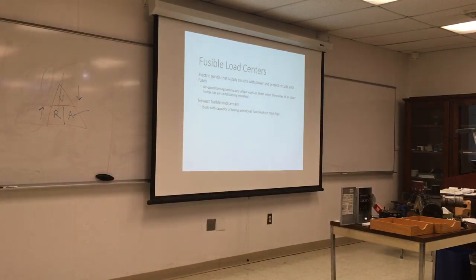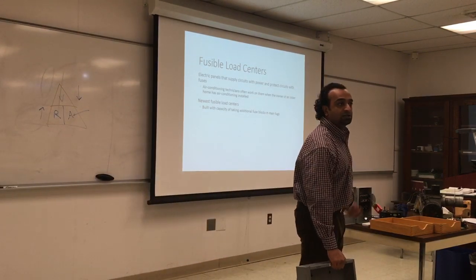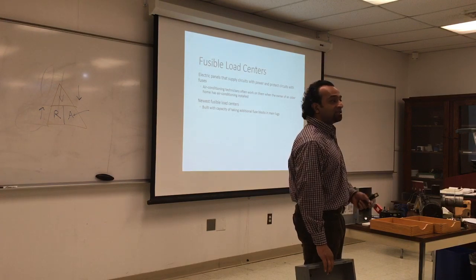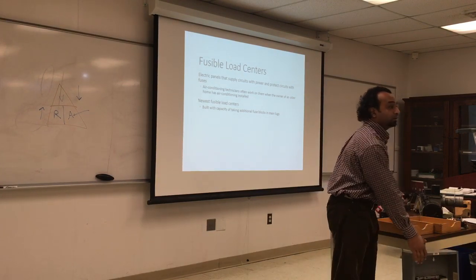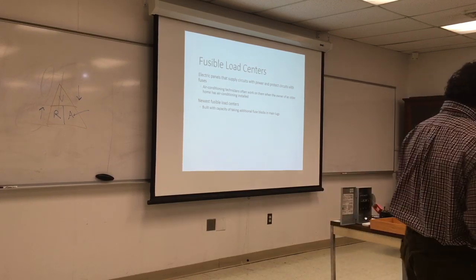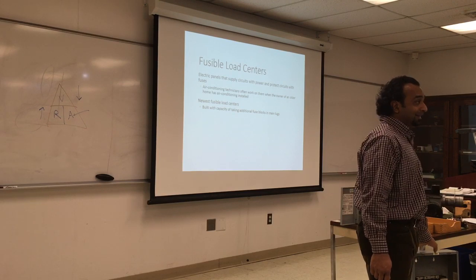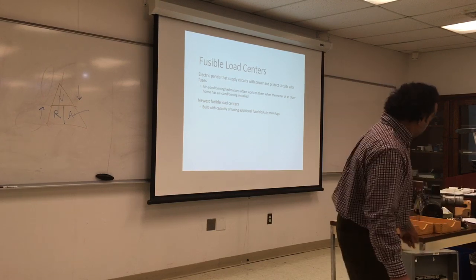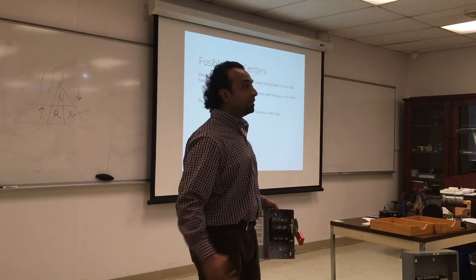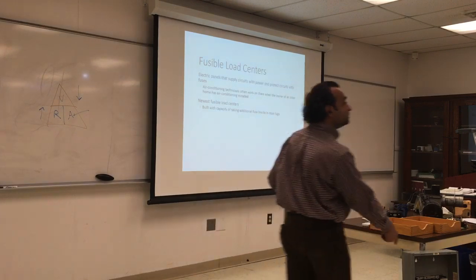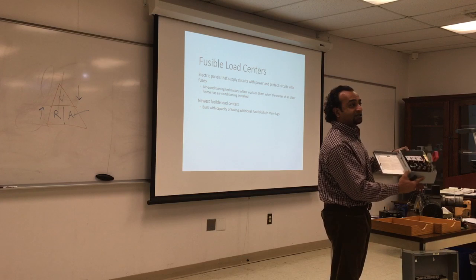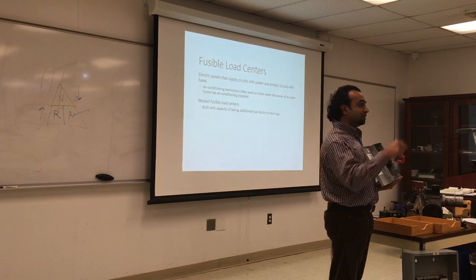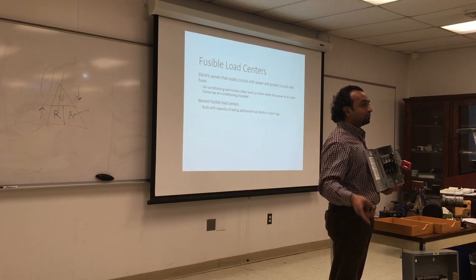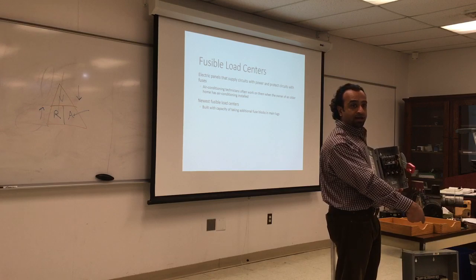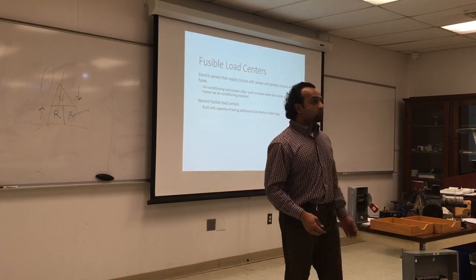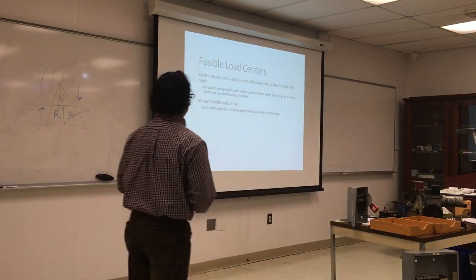Same way, we have those control panels in one place, so you know where the control panel is and you can go and shut off every piece of equipment. So it's a good idea to have things centralized and labeled. If you install a boiler or an AC and the control panel is not labeled, you cannot find the label for your disconnect switch. Label the control panel, because it is more accessible than the disconnect switch. Where would I have the disconnect switch? Outside, next to the compressor, very close to it. It's really difficult to go and find the disconnect switch outside. It's easier to go to the control panel and close the disconnect switch. So that's why we try to have them all in one place.